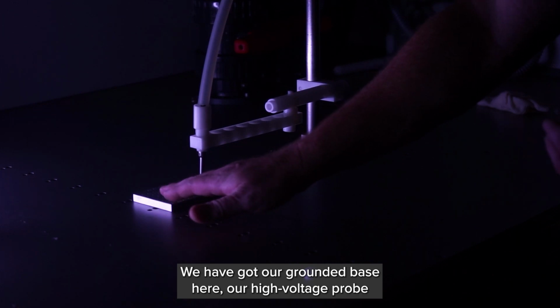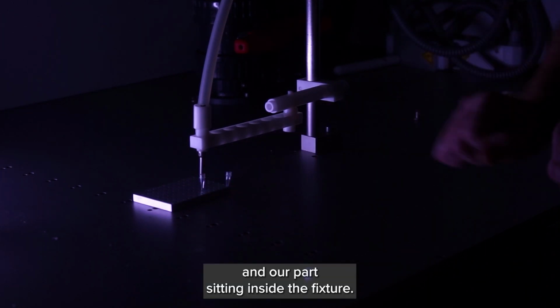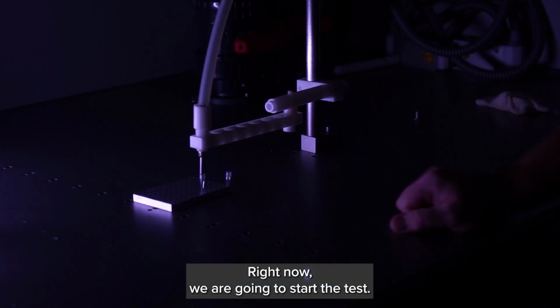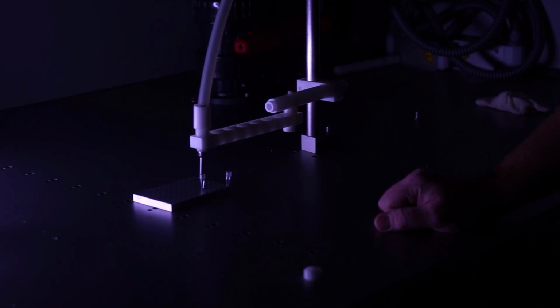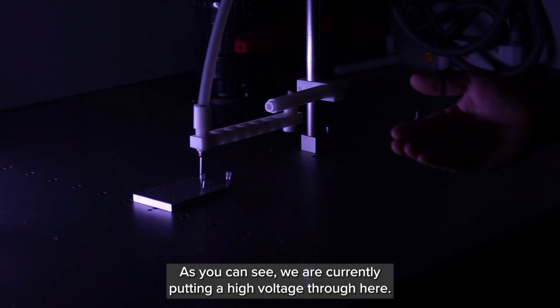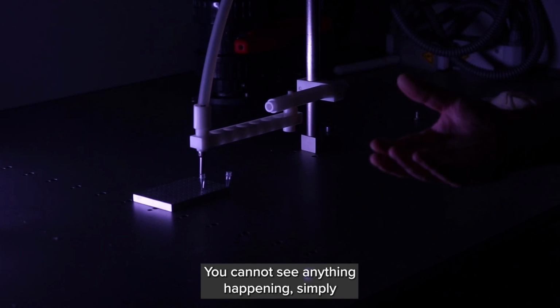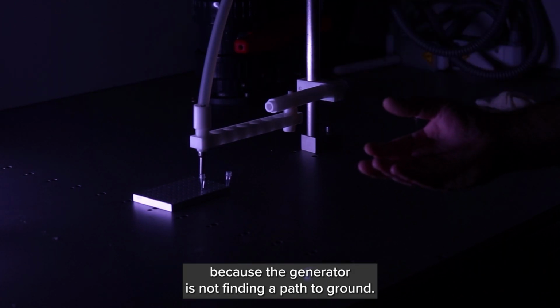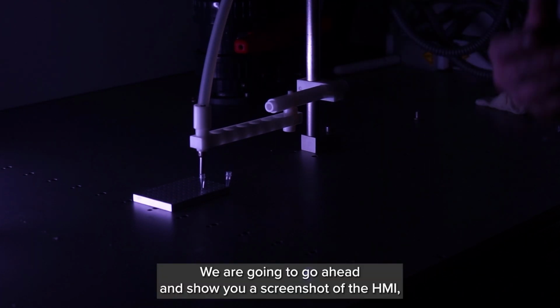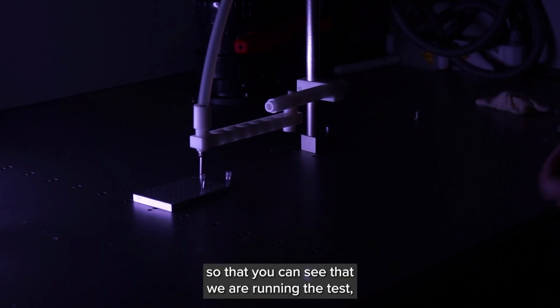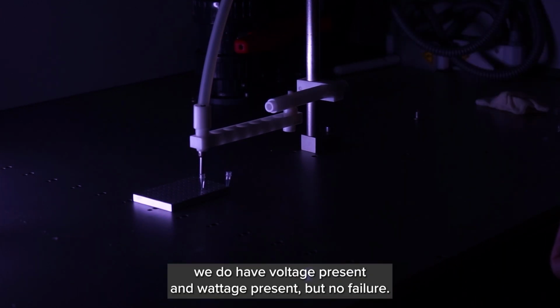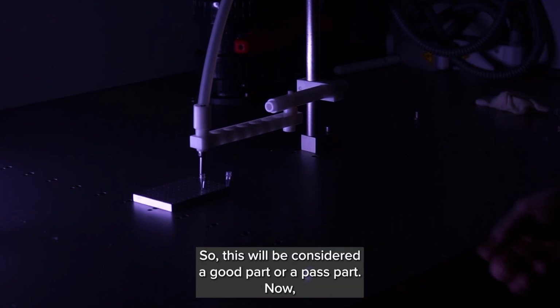We've got our grounded base here, our high voltage probe, and our part sitting inside the fixture. Right now we're going to go ahead and start the test. As you can see, we're currently putting a high voltage through here. You can't see anything happening simply because the generator is not finding a path to ground. We're going to show you a screenshot of the HMI so that you can see that we are running the test. We do have voltage present and wattage present, but no failure. So this would be considered a good part or a pass part.